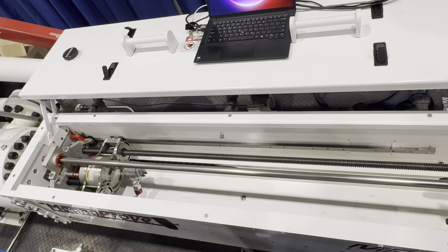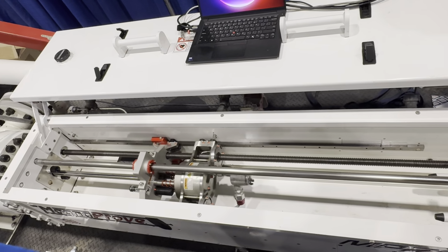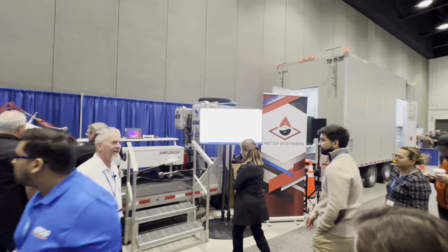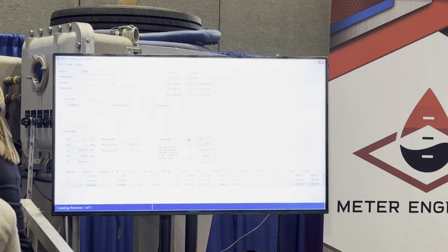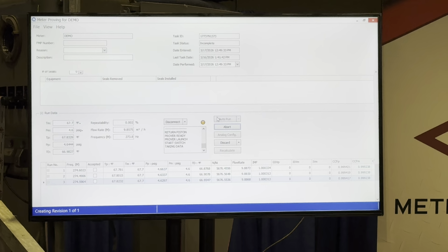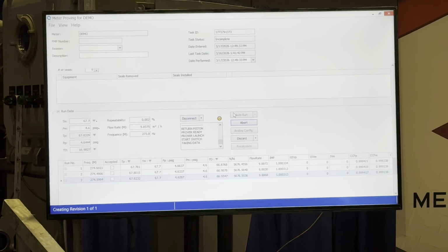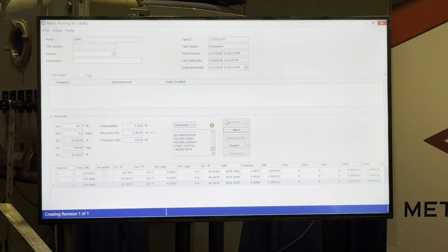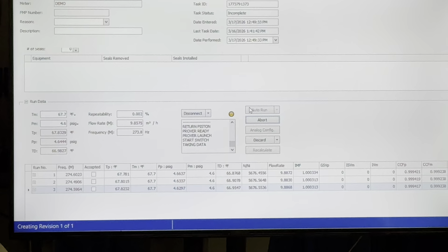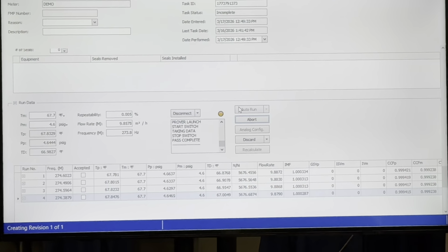I need a repeatability of... It's really about manufacturing precision. Not every time you'll get 5 straight runs, 5 out of 5. More times than not, for some reason, the first pass usually kicks out just because something isn't stabilized or something like that. But best case is if you get 5 out of 5. Some people run the uncertainty where they can go 3 to 20 passes. Whenever it gets to .027, they'll accept it.